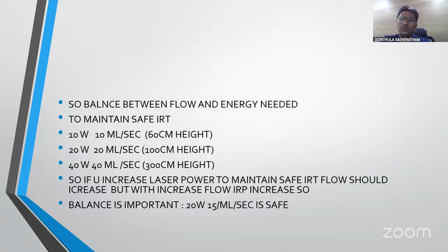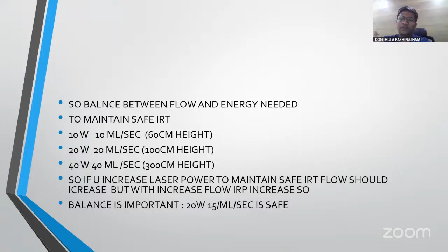But you have to assess IRP also, not IRT only. Because if you are using high energy levels and you increase the flow, you may decrease the temperature, but at the same time it will increase the intrarenal pressure. So there must be a balance between the energy and flow. After all these discussions, what you can come across is that if you use 20 to 30 watts, lesser energy with lesser flow, approximately 15 ml per second, it will be safe both for pressure and temperature.